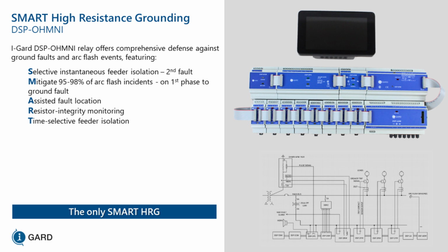We can mitigate 95 to 98% of all arc flash incidents because it's a high resistance grounded system. We can help you locate where the fault is. The A is assisted fault location. R, resistor monitoring. In Canada now, there's a code requirement that says you have to monitor the integrity of the resistor. We've always had it in mining, but now it's in the Canadian Electrical Code, so you have to do that throughout. And time selective feeder isolation.